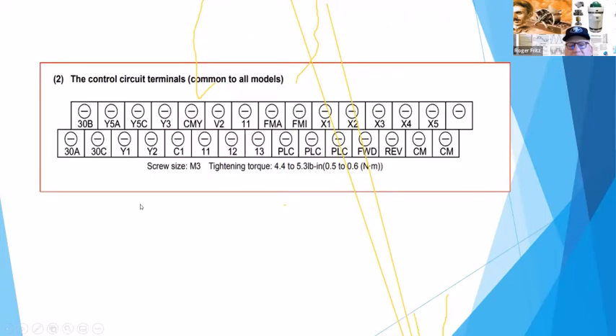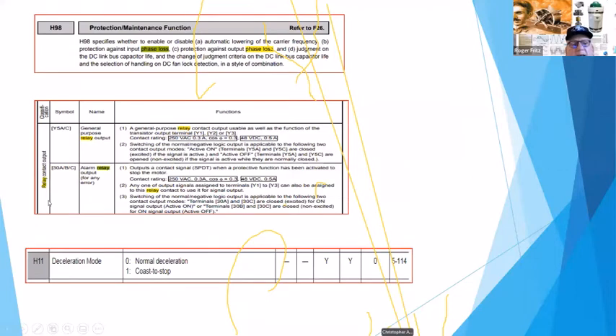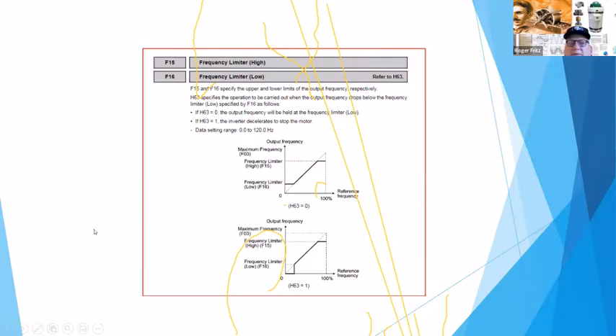Your status, source. And then inside they have a set of control terminals that are, again, like a PLC, where you have contacts here. Your 30s are just an extra output relay. So is the Y. Then you have your various X inputs. So as you go common to X1, it gives a run command. You can set X1 to be a run, a stop, or it gets multiple parameter issues. They come out as standard. And if you look at a drive, most of them have what they call quick start. So you can quickly start the item. Let's see, this shows just a few of the various assignment pieces of those contacts, like here, the Ys, the relays, of what you can do with them. You've got your acceleration, your deceleration, whether you want the motor to coast to stop or ramp to stop.